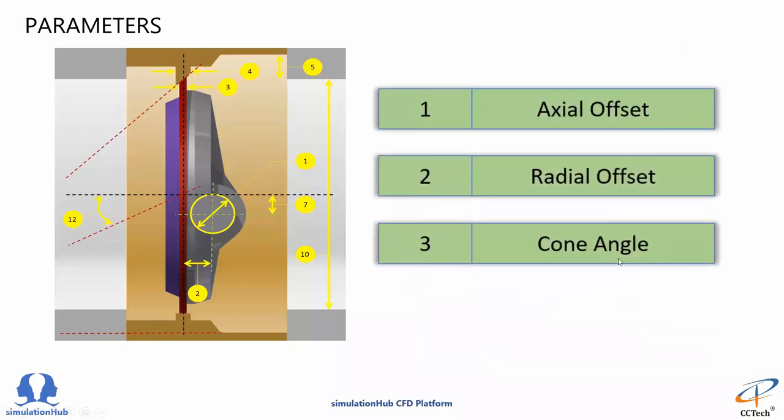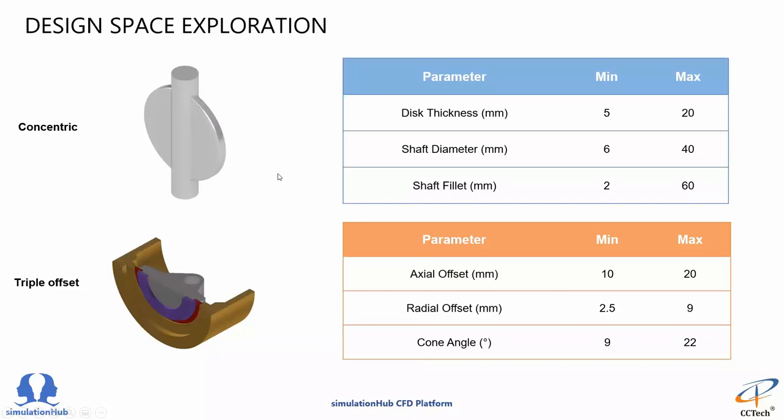For a triple offset valve, the three offsets are the highly influencing parameters for Cv. We were able to achieve results in just a month. So reducing the complexity always works. We did the same with concentric butterfly valve and chose these following parameters: the thickness, diameter and its fillet. As we wanted to predict Cv for any size of valve with the app, we added a fourth parameter that was the diameter of the valve, the size basically.